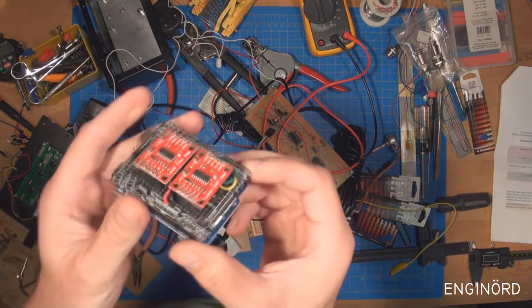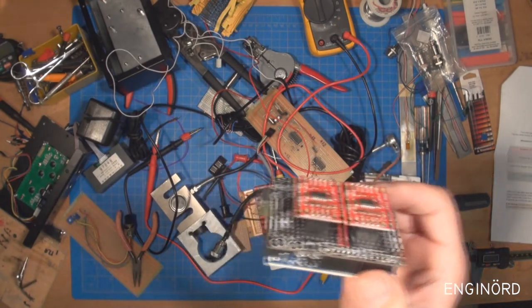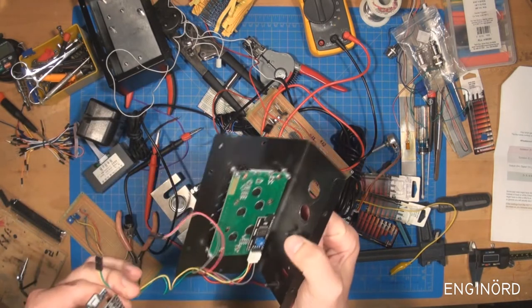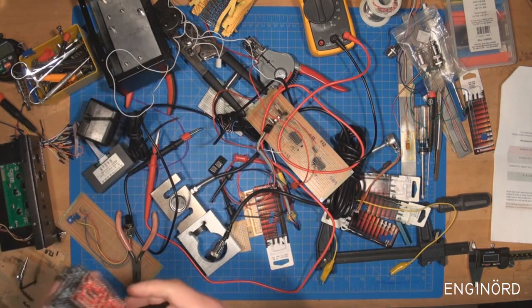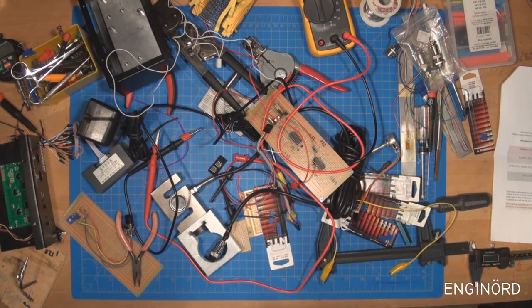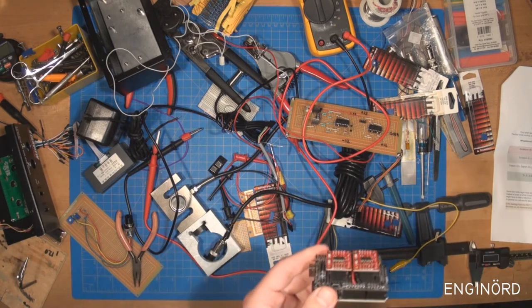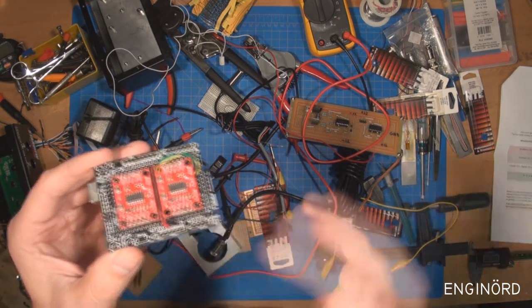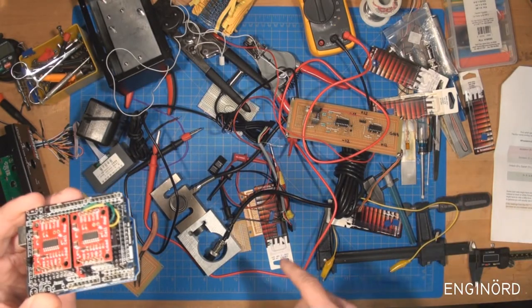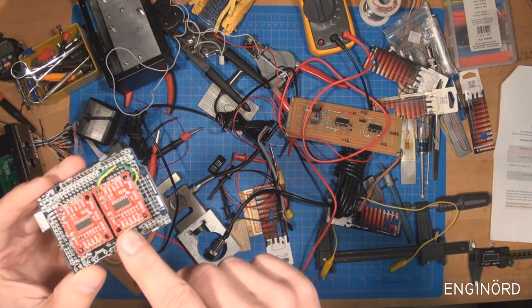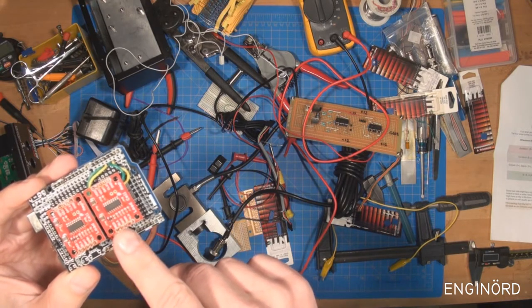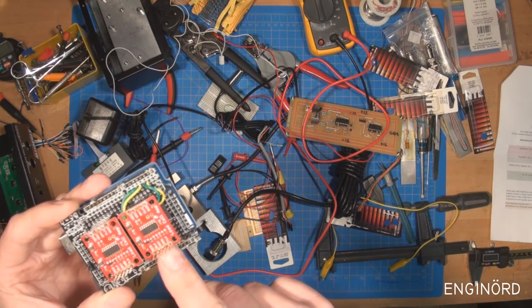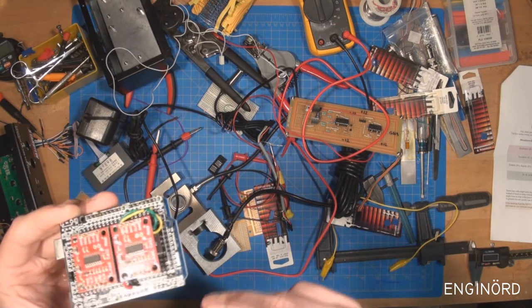So what I created here is pretty straightforward. I got these pins here. So initially I had some female connectors that connected to this one. It's just a standard 5 pin connector. So why do we have 5 pins when you only have 4 wires? So the 4 wires are red, black, white, green and yellow. So the red and black, those are the excitations. So 3 volts or 5 volts, 10 volts, whatever you use. And then the white and green, those are the output or the sense wires sometimes they call it. And then the yellow is basically chassis ground.